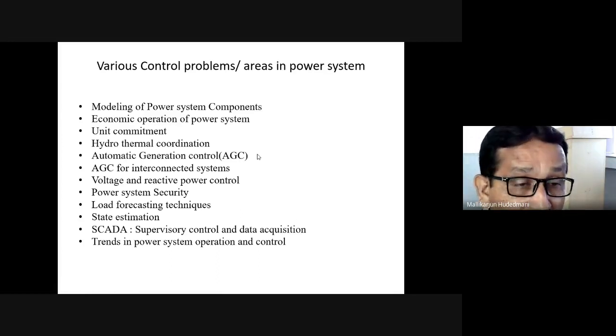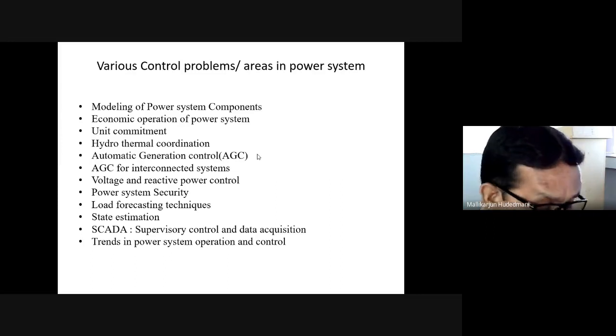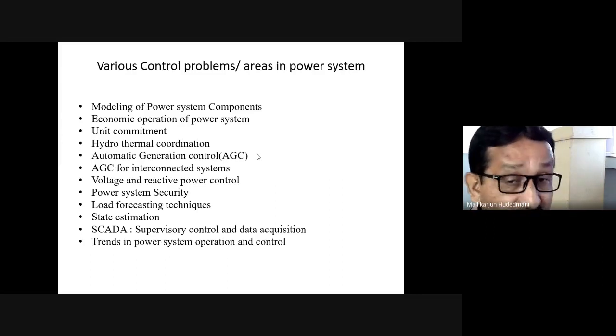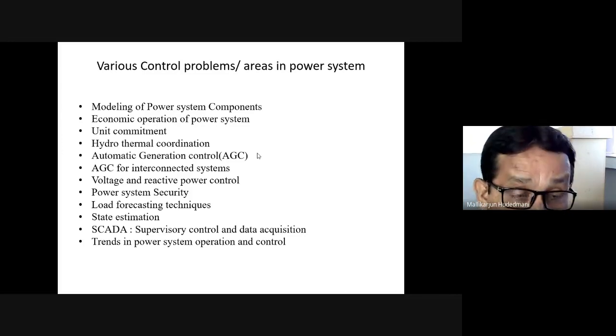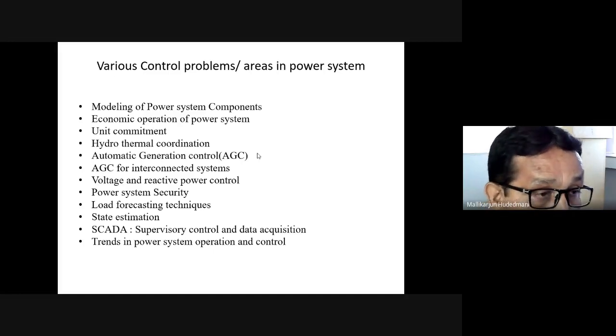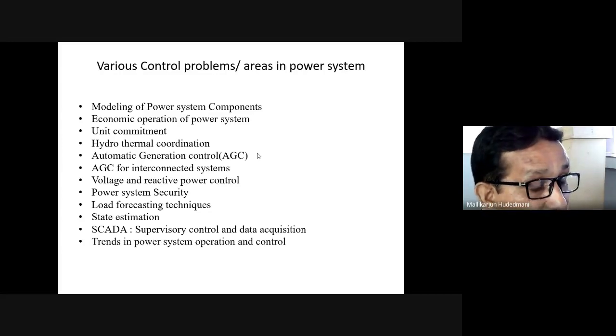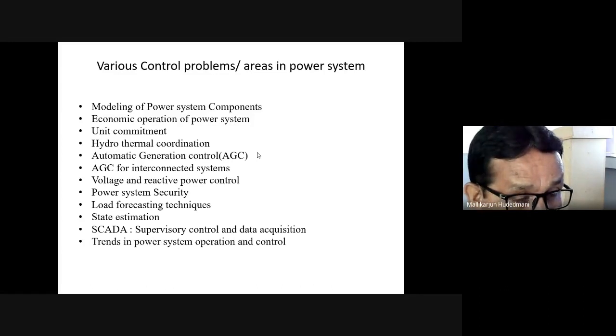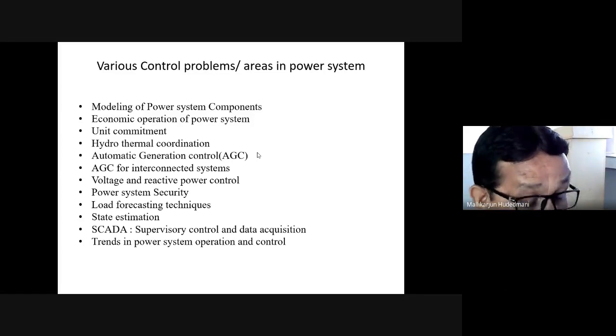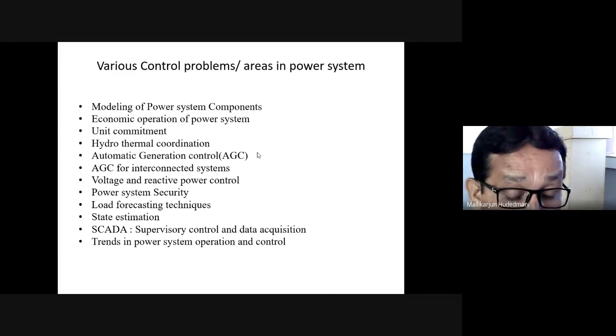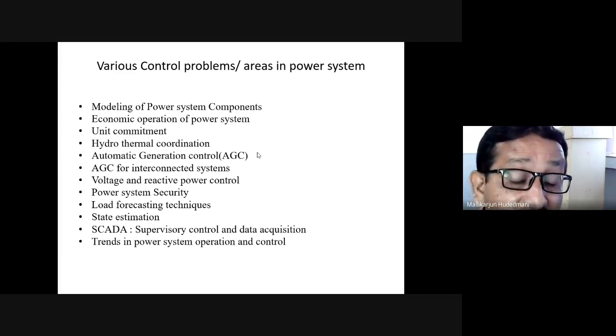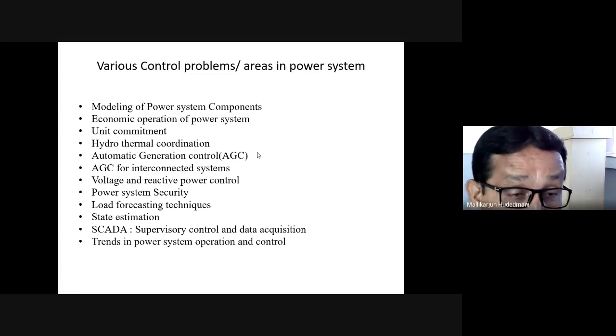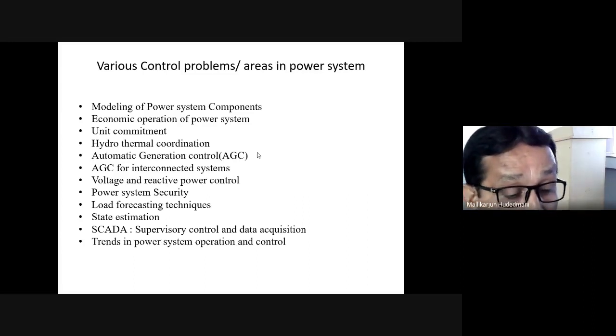How is that? The synchronous generator is monitored and controlled so that generation meets the requirement effectively. That control setup always keeps an automatic voltage monitoring, called the automatic voltage regulator, AVR, monitoring the voltage irrespective of whether there is load or no load on the station, so that terminal voltage is maintained appropriately by excitation control. On the other side, from the turbine, the fuel input is managed to see that the RPM of the turbine is maintained such that frequency is kept constant.